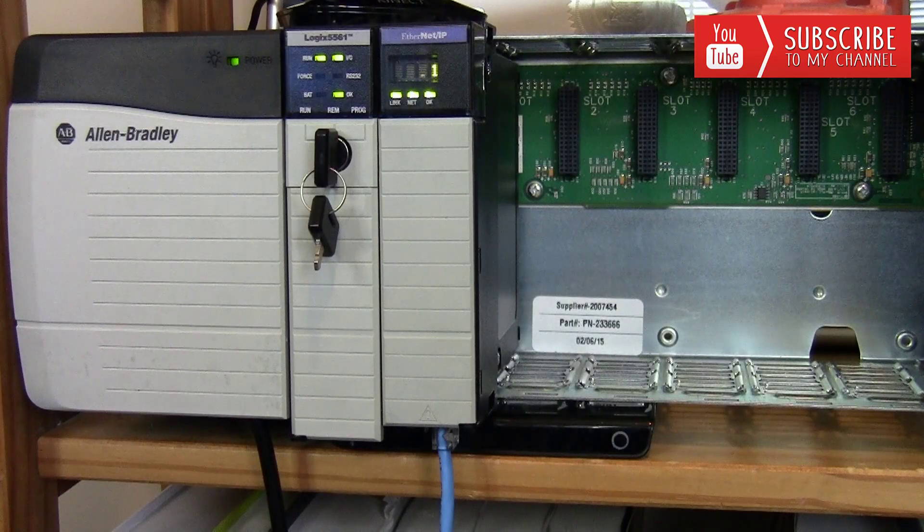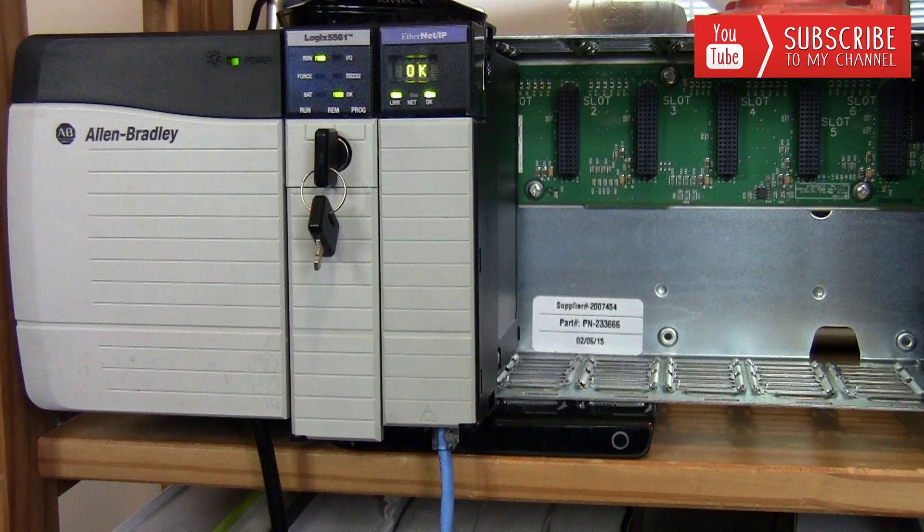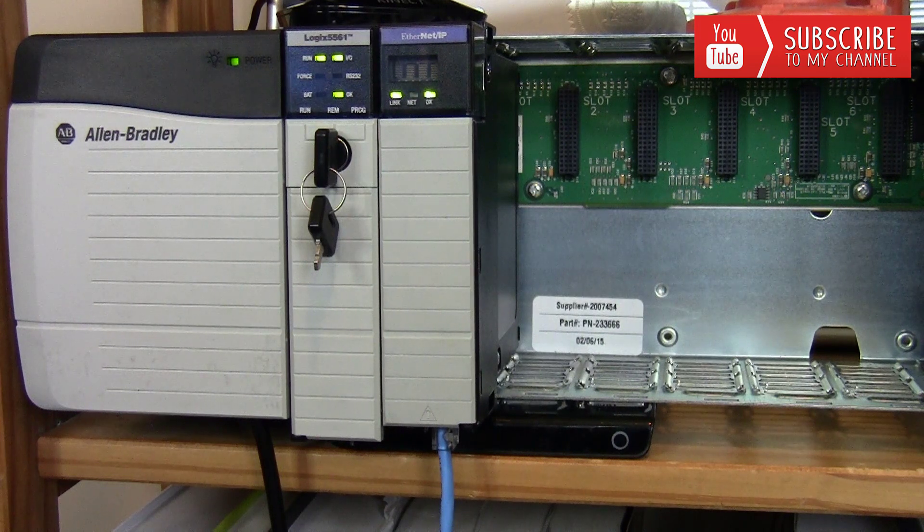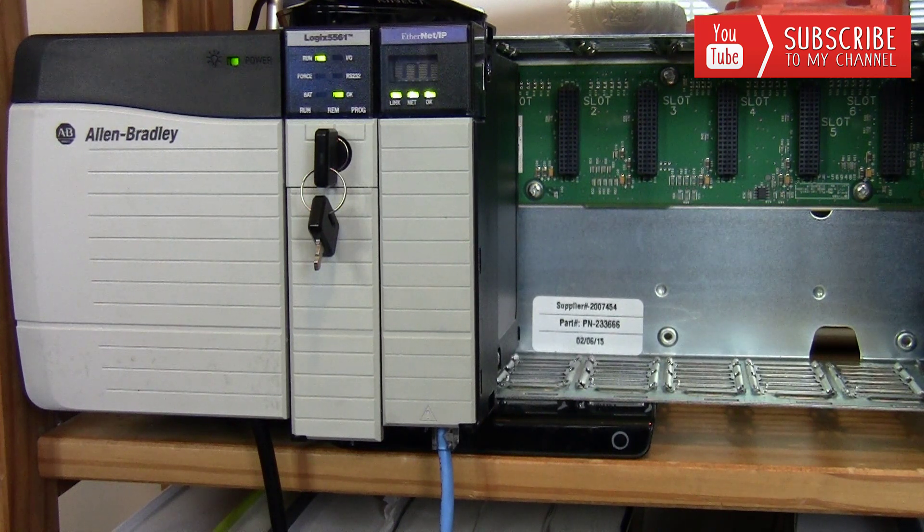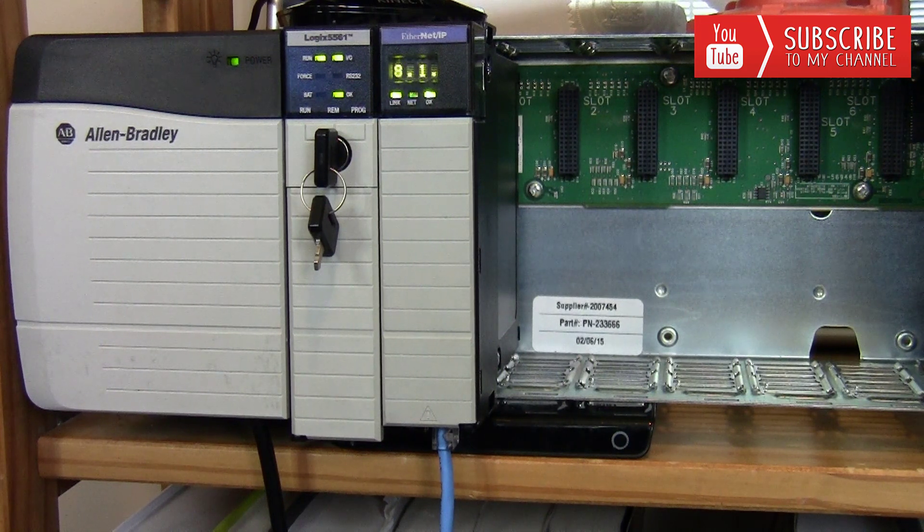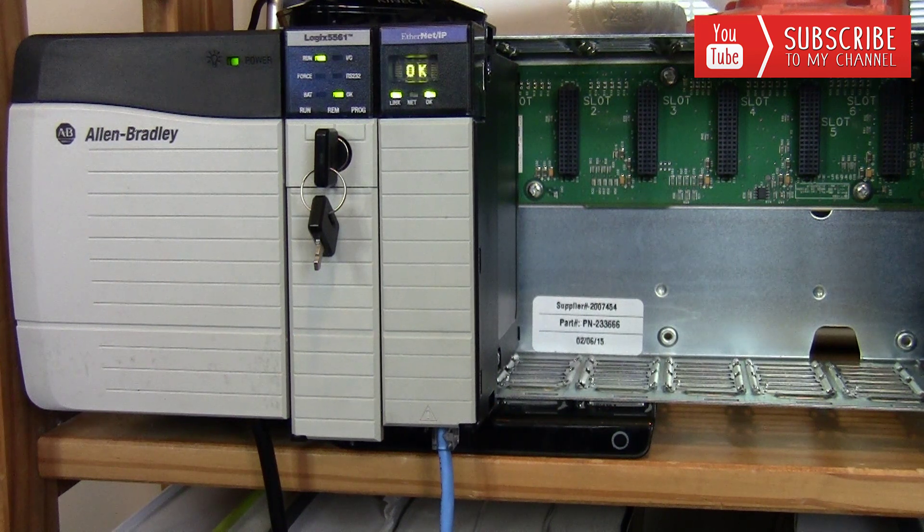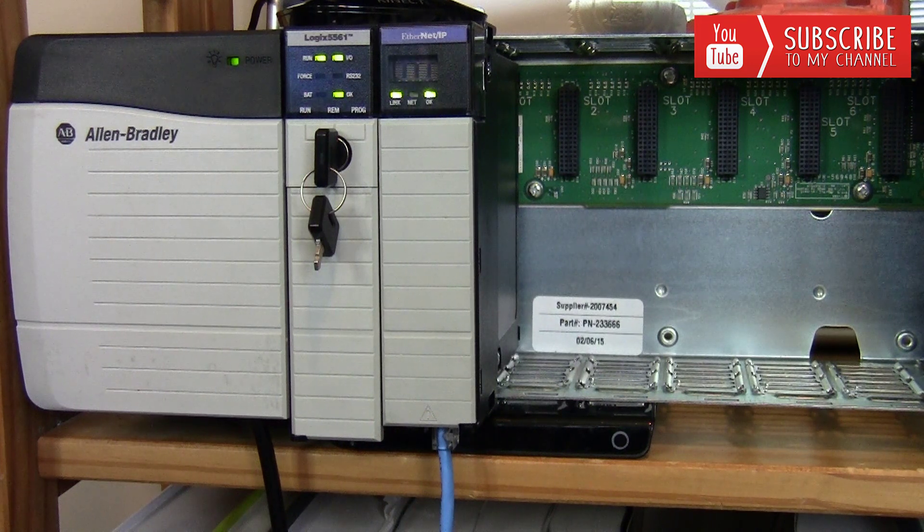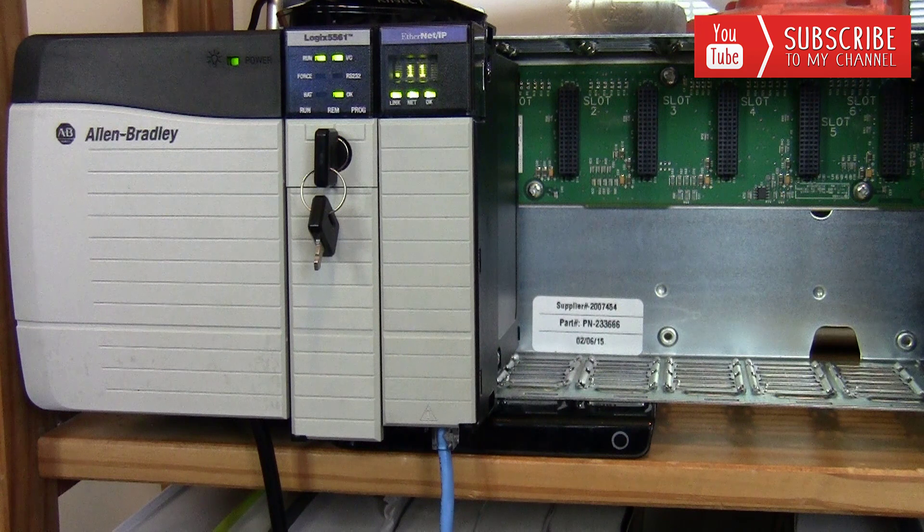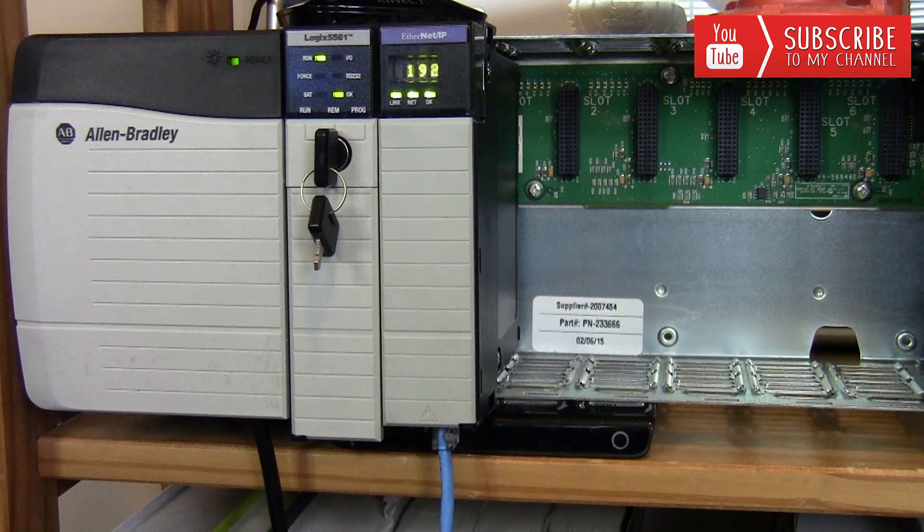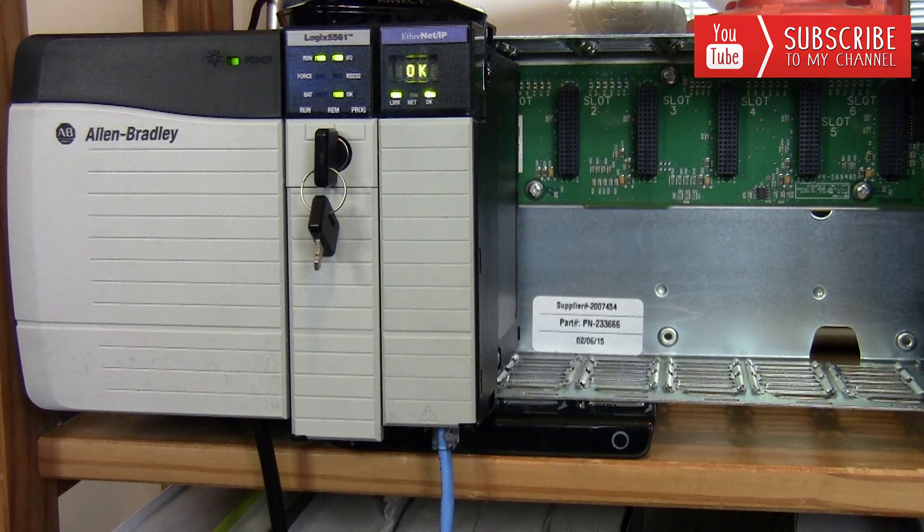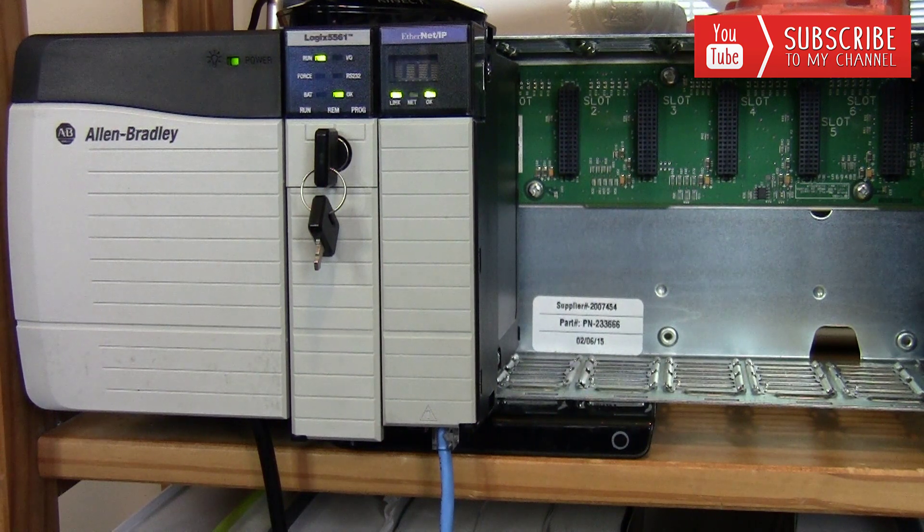You can see here I have a 1756-L61 processor residing in slot zero of my chassis, and right beside it I have a 1756-ENBT module that will allow me to communicate to the processor via ethernet. Since we're downgrading the firmware, it's safe to assume this infrastructure is already set up so we can go through an ethernet channel. Its IP address is 192.168.1.11 and we're going to configure that ethernet driver in RSLinx to communicate to that processor so we can downgrade the firmware that's currently at version 20.